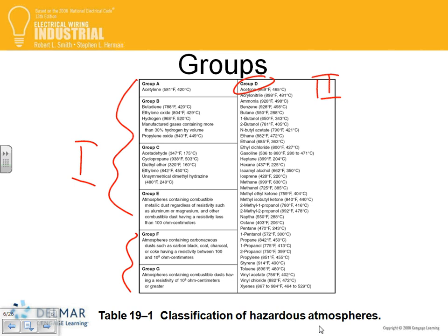So if anybody wants to read and look at the temperature that it takes to ignite, they have a temperature for every gas. If you reach this temperature, that gas will ignite. Yeah, it's on page 247, not in Delmar. So when you're dealing with this, guys, if it reaches 581 Fahrenheit, this gas will ignite.